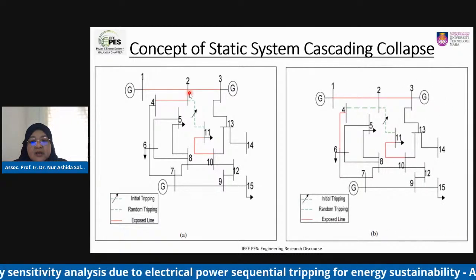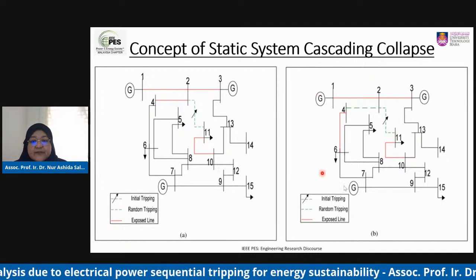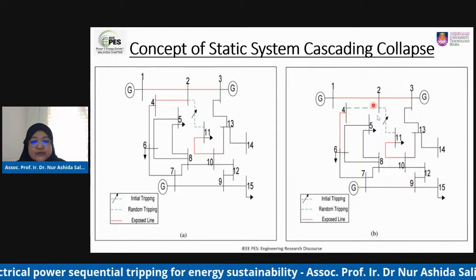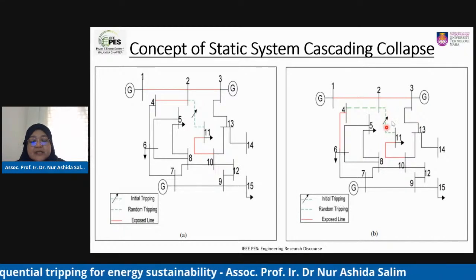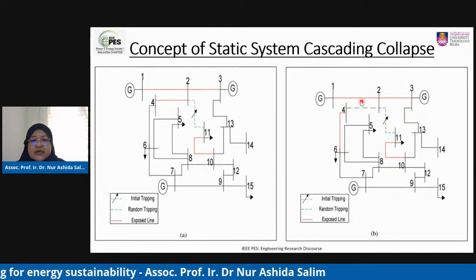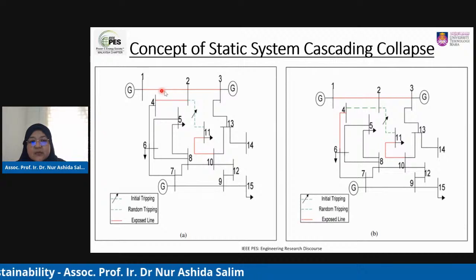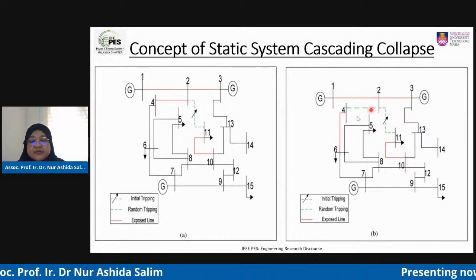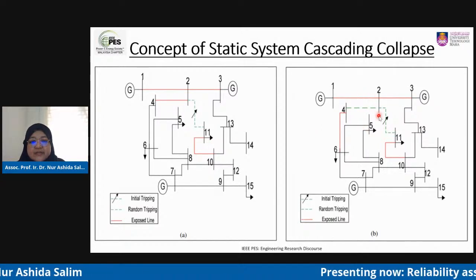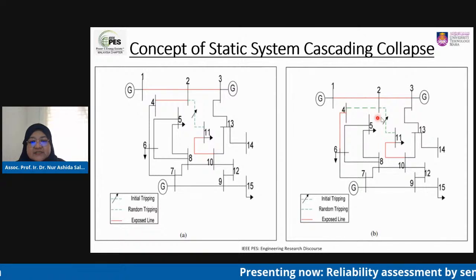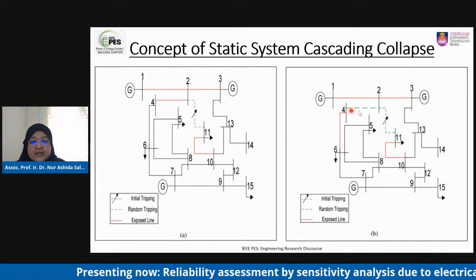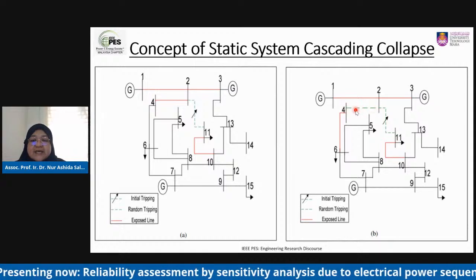So let's say after performing the load flow study, we have the initial line tripping just now. Out of these four exposed lines, after performing the load flow, it seems that the line from bus 2 to bus 4 violates the thermal limit.